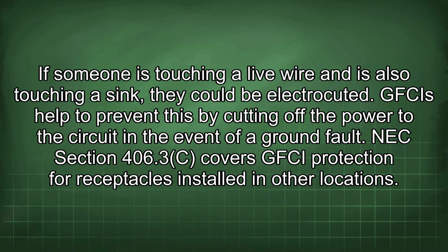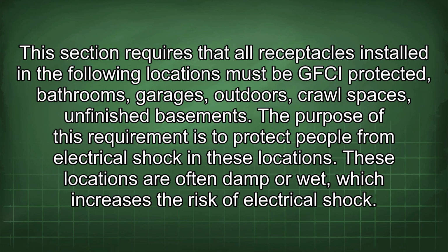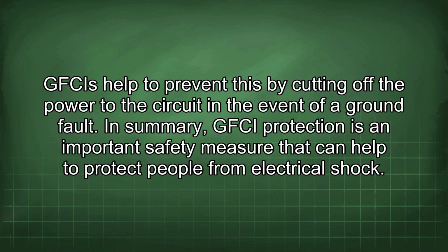NEC Section 406.3c covers GFCI protection for receptacles installed in other locations. This section requires that all receptacles installed in the following locations must be GFCI protected: bathrooms, garages, outdoors, crawl spaces, unfinished basements. The purpose of this requirement is to protect people from electrical shock in these locations. These locations are often damp or wet, which increases the risk of electrical shock. GFCIs help to prevent this by cutting off the power to the circuit in the event of a ground fault.